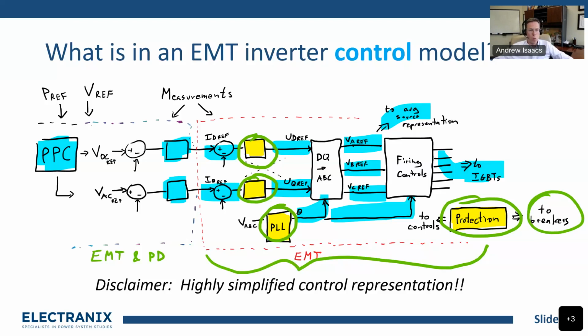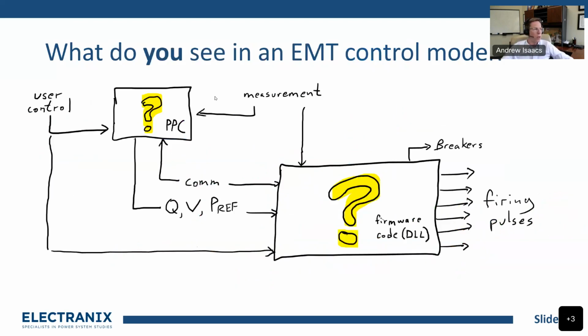So when you have fast events happening in the system, or you have a moment when the converter needs to respond very quickly, or respond to a very severe event in the system, these guys all come into play. And that's why we're looking for an EMT model when we're trying to understand exactly how a plant responds to a fault. What you see in an EMT control model, if you get one, is not going to look like that. It's going to be black boxes, right? They're not going to show you what's in there.